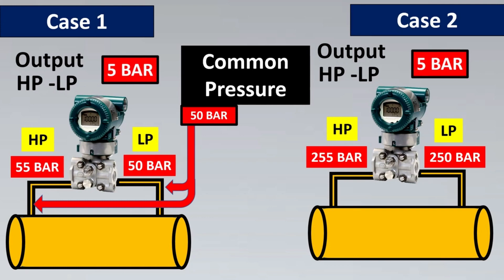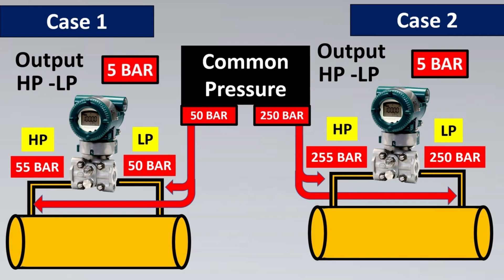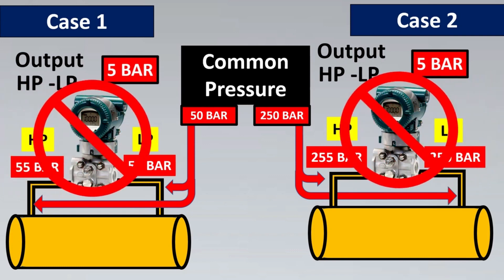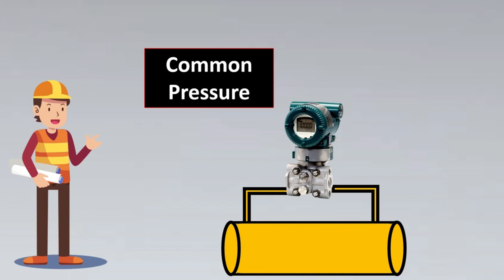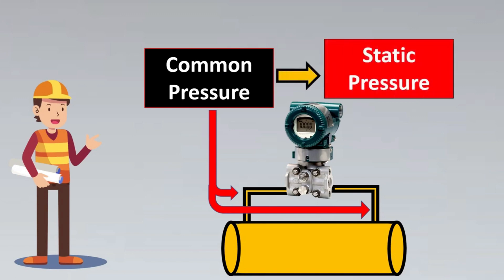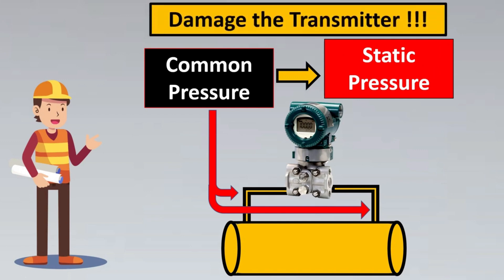There is something called common pressure. In the first case, 50 bar is commonly hitting both legs of the transmitter, while in the second case, 250 bar is commonly hitting both legs. This pressure that hits both legs at the same time of a DP transmitter is termed as static pressure in the engineering world.